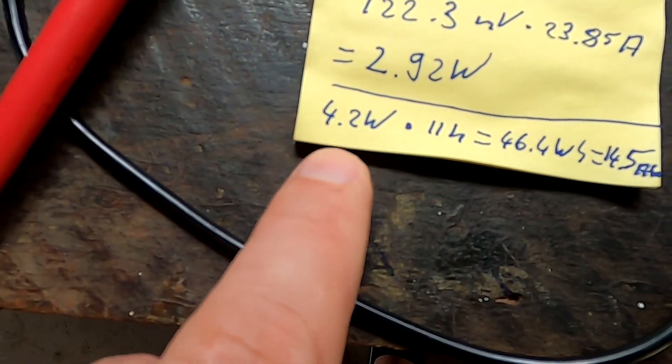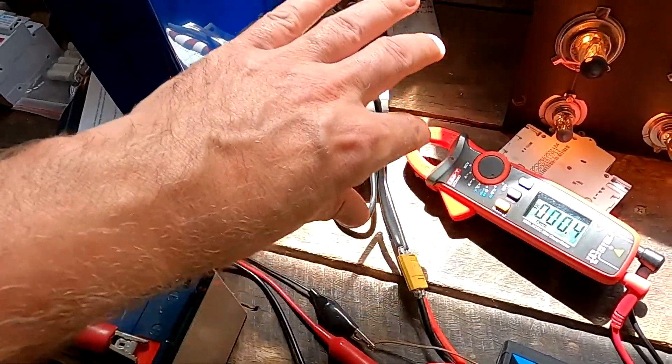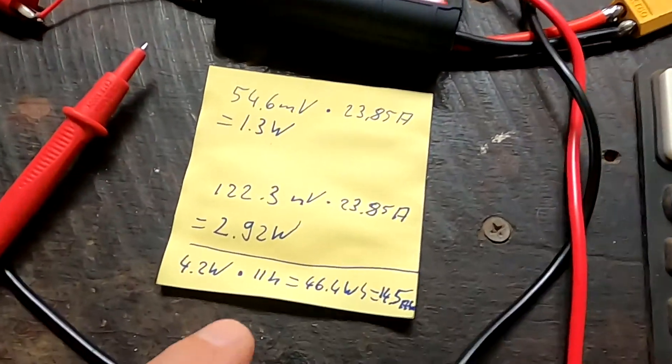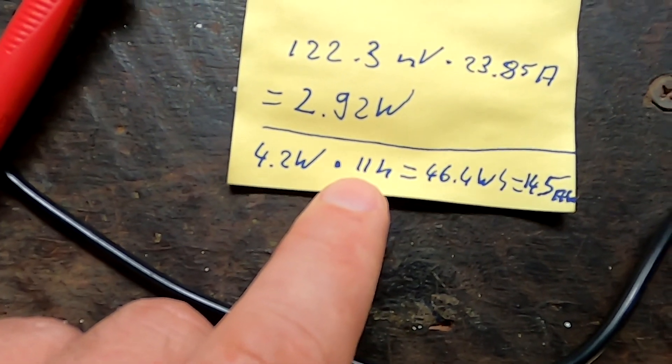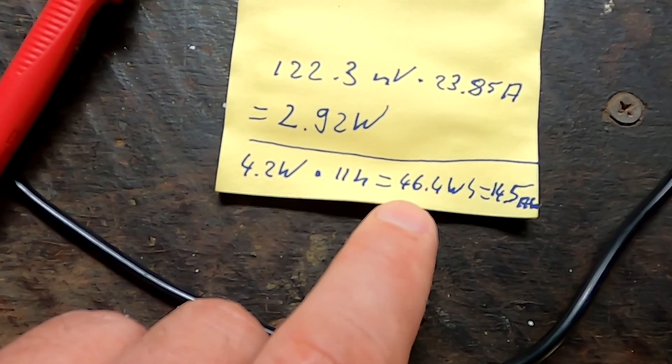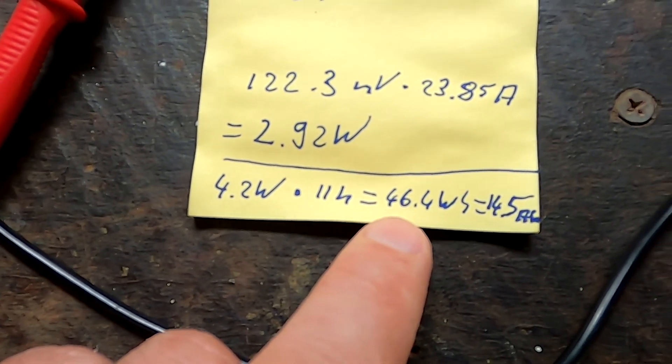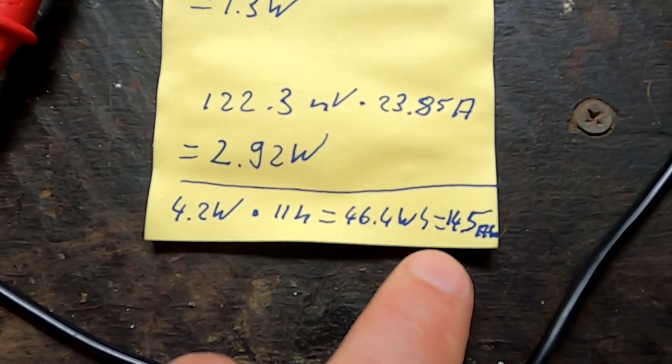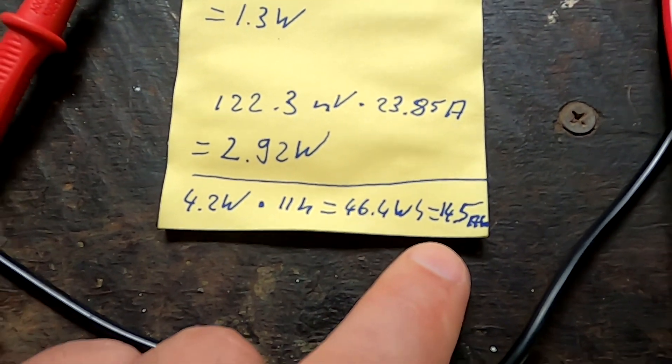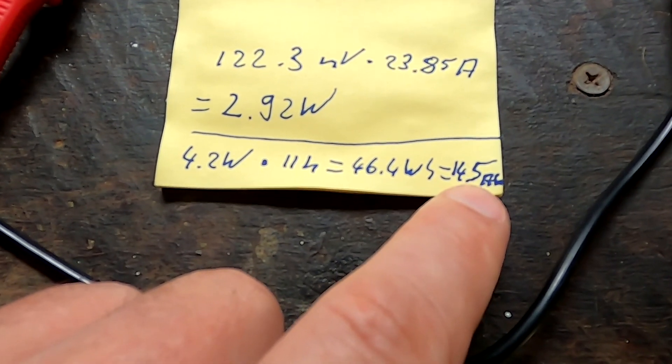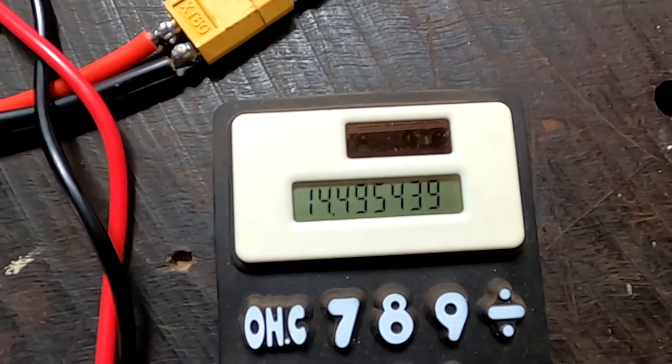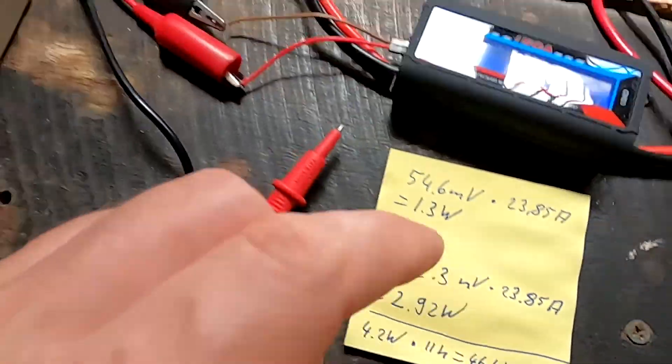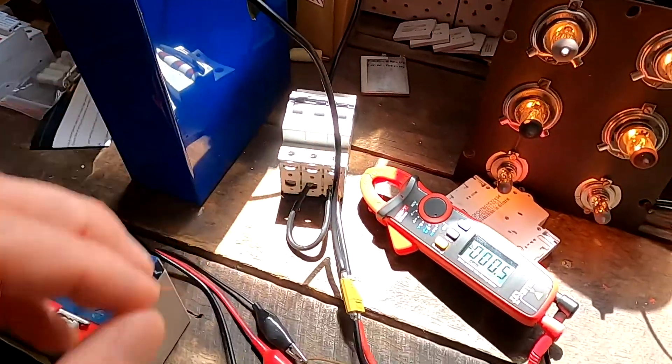Times 11 hours that the test was running on Sunday, this results in 46.4 watt hours. Divided by 3.2 volts, that's 14.5 ampere hours lost just on these cables.